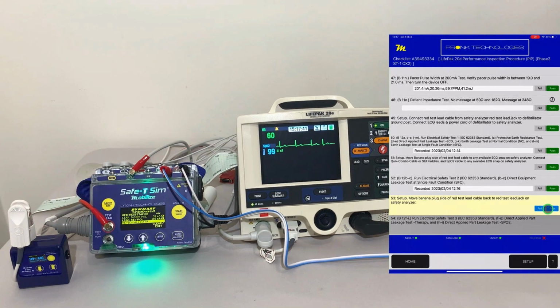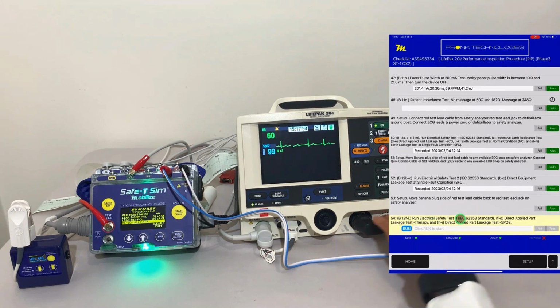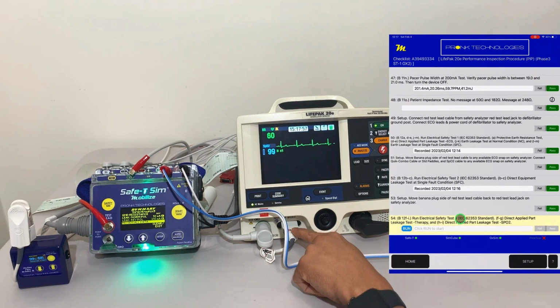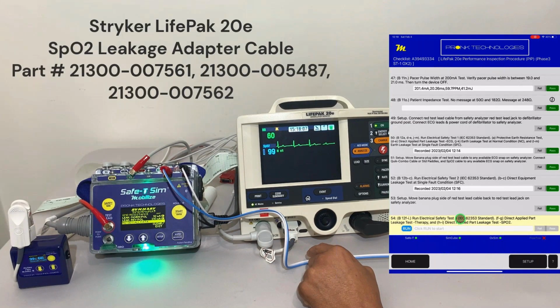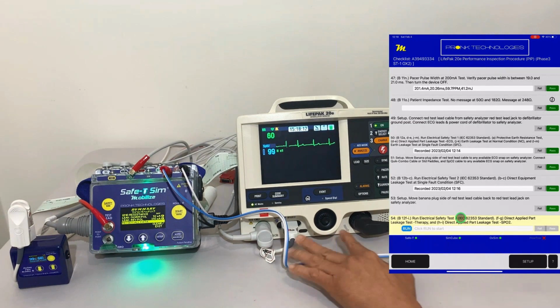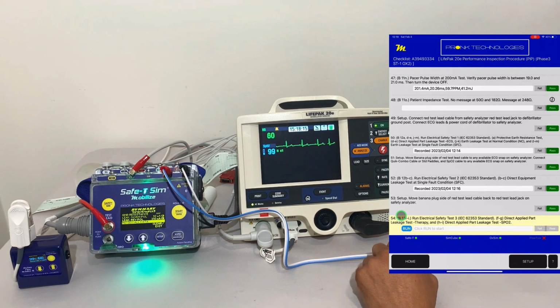The last test is to do what's called the direct applied parts leakage test for the therapy and the direct applied parts test for the SpO2. So the therapy cable is considered to be this quick combo cable. And of course, we want to do a leakage test on this SpO2 port. Per the manufacturer's recommendation for this adapter cable they require to use, you'll find the part number in the service manual. We'll post it here as well in our video for you. And so we've got the test leakage for these things as well. So we've got that electrical safety analyzer configured to do this test, and we're going to run that next test.